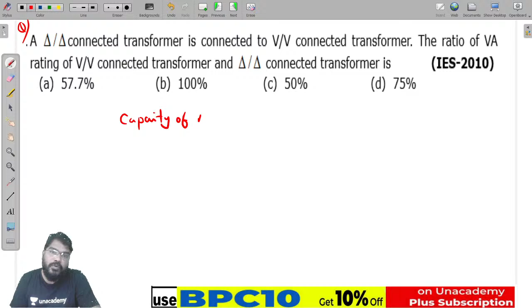So the capacity of the open delta connection is equal to root 3 times V phase and I phase. Now the capacity of the closed delta is 3 times the V phase and I phase value. These will be cancelled out. The V phase and I phase are cancelled out.